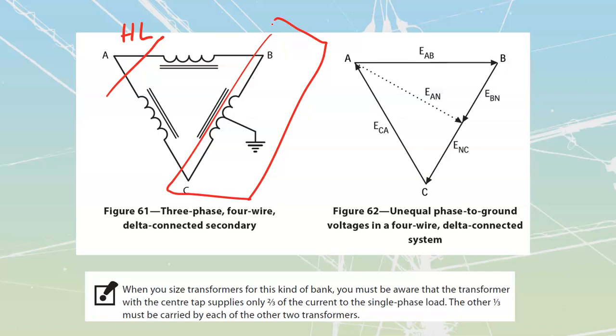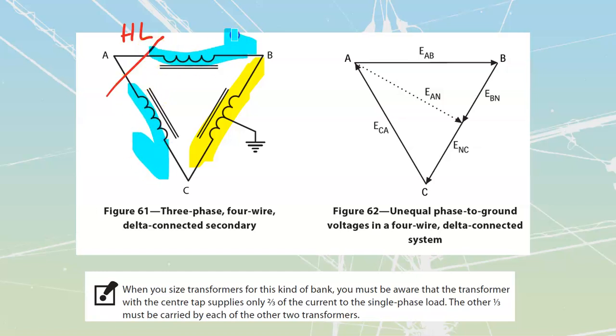If you do go with this 4-wire delta connection over here, you do have to watch the amount of power that is going to be put out by your different windings, because they are going to become unequal. I've taken a snip of what that says inside of your book. It says that this winding over here is going to supply 2/3 of the current to the single phase load, and the other 1/3 is going to be taken by the other two windings. Not at the same time, so they're not each getting a 1/6, but this one's going to be delivering that last third, and then the other one, and then the other one. They're just going to alternate back and forth who's delivering that last third.